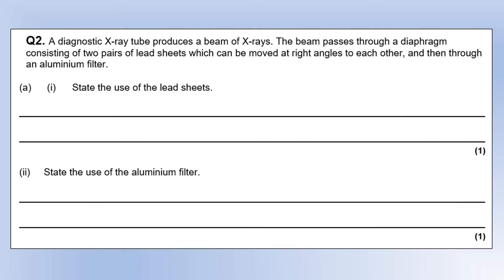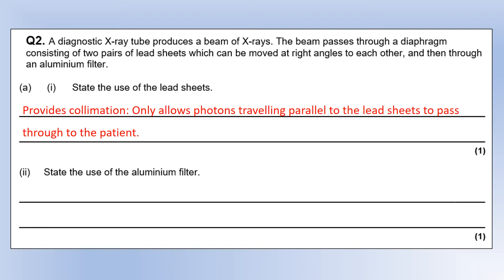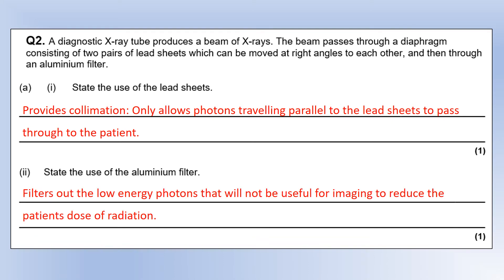Now looking at x-rays from a different perspective: after x-rays leave the tube, they pass through a diaphragm — two pairs of lead sheets movable at right angles to each other — and then through an aluminium filter. The lead sheets provide collimation, allowing only photons traveling parallel to the sheets to pass, producing a fine beam directed exactly where needed. The aluminium filter removes lower-energy photons that aren't useful and would add to the radiation dose.